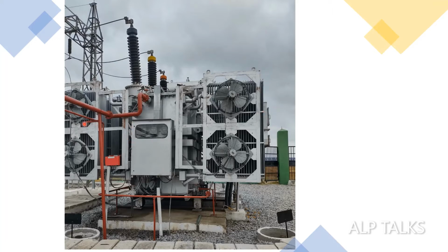We have NIPS system also. Generally it is mandatory in generating stations. We can see the NIPS system is connected at the bottom at two different places, and at the top at one place. Here we have fans arrangement. The fan arrangement, everything we will discuss in our next sessions also. Here we can see the earthing arrangement. So earth pit, everything is fencing and all, we can observe here. Here we can observe the terminal lugs and all, the connectors, how they are connecting the bushing and the outside lead. It is very good to observe.